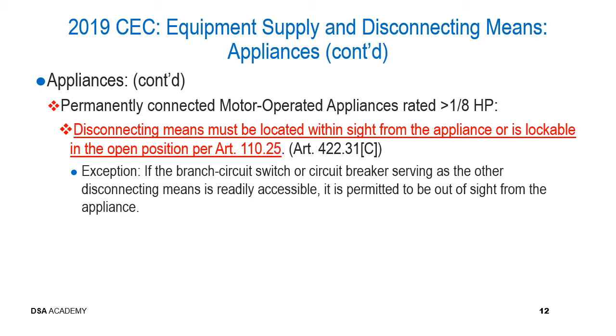422.31(C). And again, what you can see is the California Electrical Code has basically adopted this same protocol for having a disconnect that is not within sight of the appliance, that is lockable in the open position. Now there is an exception to this, and that exception states if the branch circuit switch or circuit breaker serving as the other disconnecting means is readily accessible, it is permitted to be out of sight from the appliance. So remember, that's readily accessible.